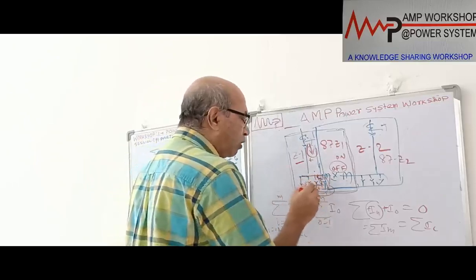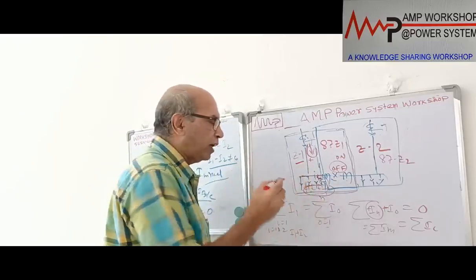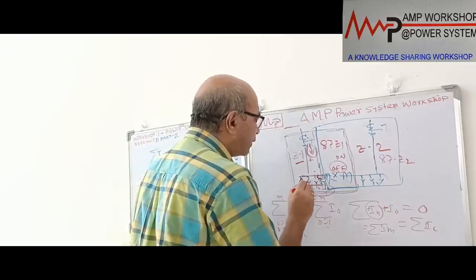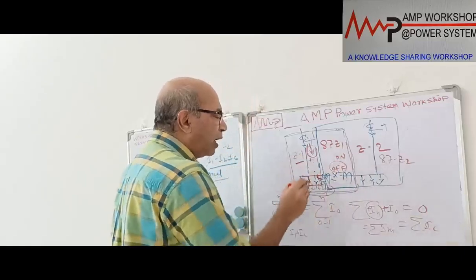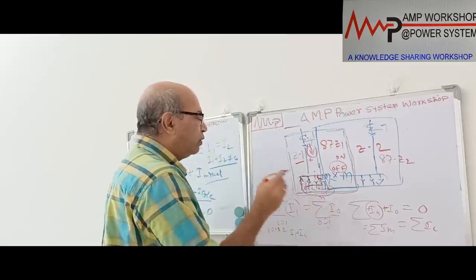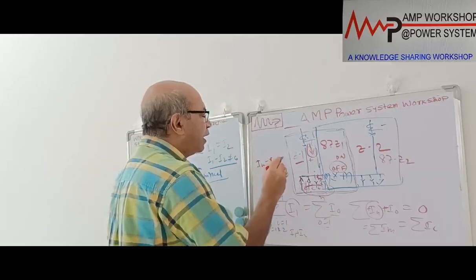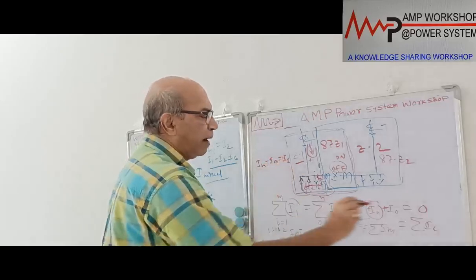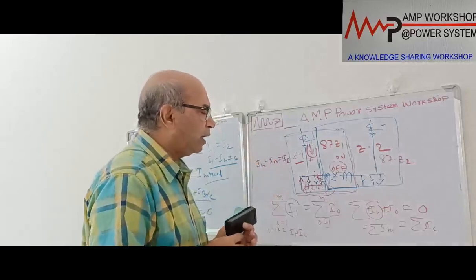At that time, the normal feeders will be at 0 under voltage, and the motor feeders or the source feeders which can produce current will be feeding power to this bus. So that will be positive, and this negative value will become 0. So all current will be considered as input current and output current is 0. So I input minus I output equals the fault current. Then the balance equation is not matching, and immediately the relay will operate. This is the circulating current principle.